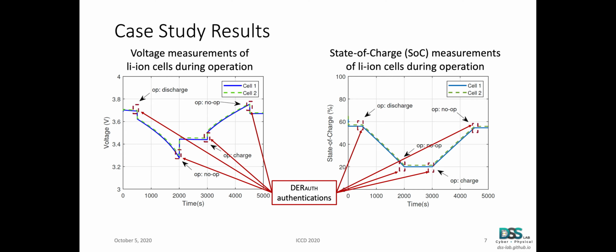These operations are a 10-watt discharge request at 500 seconds, a no operation request at 2,000 seconds, a 10-watt charge request at 3,000 seconds, and finally a no operation request at 4,500 seconds. At each of these points, DERAUTH is executed 5 seconds before the setpoint command is issued.